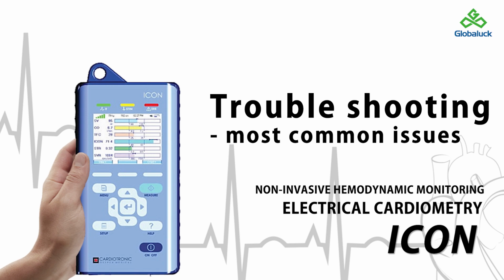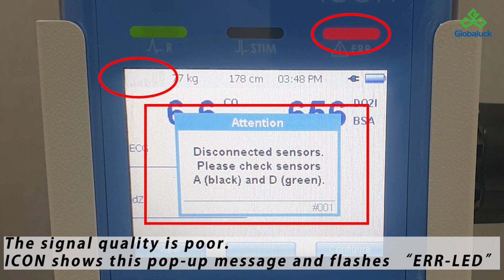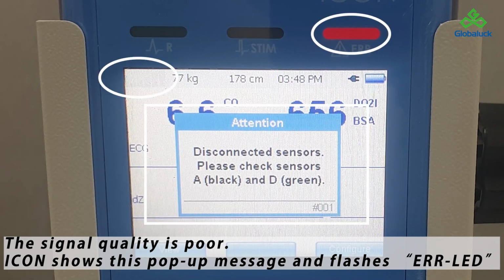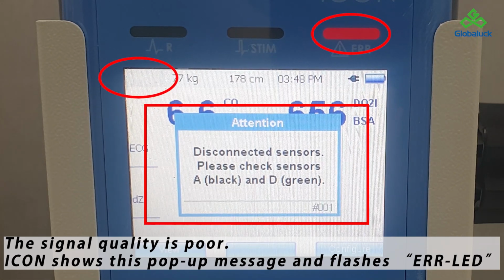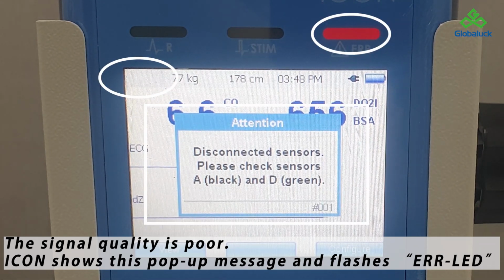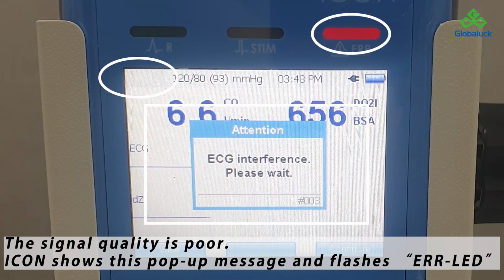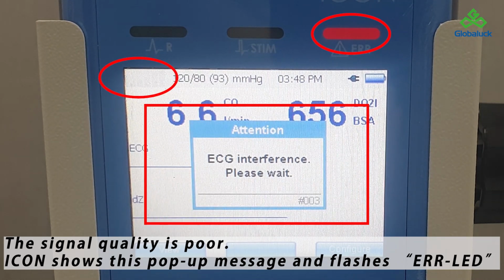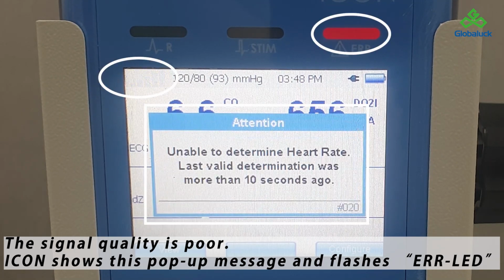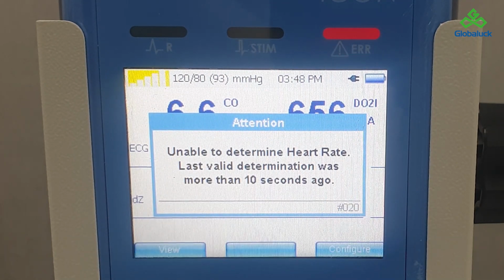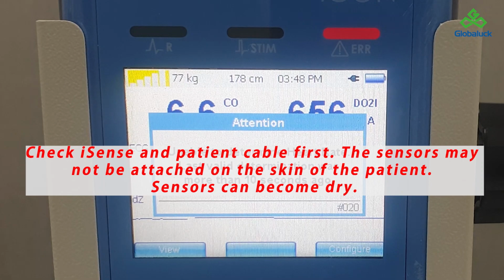Troubleshooting. We will tell you about the most common issues when you use icon. Icon shows this pop-up message and flashes a red LED when the signal quality is poor. For example, when some noises occur, or electric cautery or a defibrillator is being used, but the icon will measure again after removing the noises and no use of electric cautery or defibrillator. If this problem occurs often and for a long time, you should check the sensors and patient cables. The sensors may not be fresh anymore. Sensors can become dry. Try new ones. The patient cable may be damaged. Try a different one.